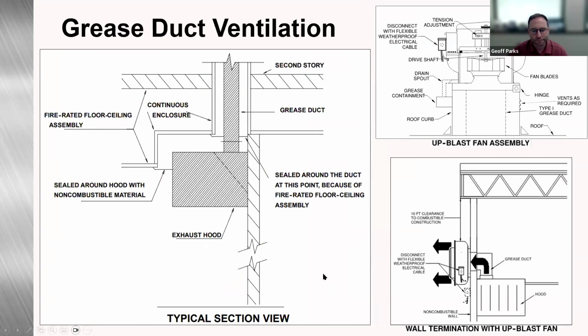So a couple of things out of the kitchen ventilation manual. We have just a typical section view with your exhaust hood, your fire-rated floor and ceiling assembly, and your grease ducts penetrating your second story. You seal around the duct at this point because of the fire-rated floor and ceiling assembly. Over in the upper right-hand corner, we have an upblast fan assembly detail. It gives you the nitty-gritty components of an upblast fan for a type 1 grease duct, and also a wall termination with upblast fan detail as well. And then 10-foot clearance to combustibles. You have your grease duct and your hood.